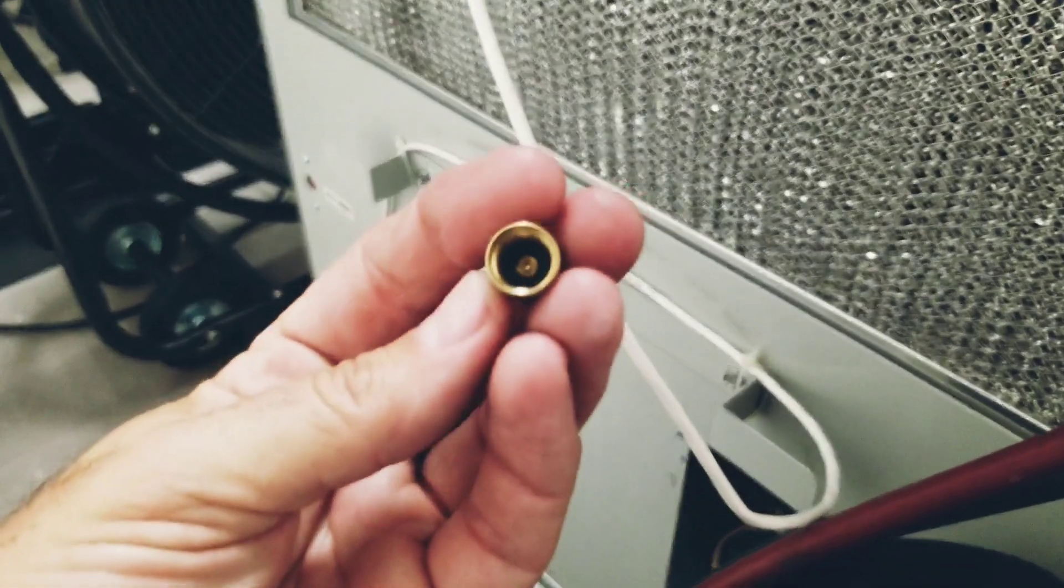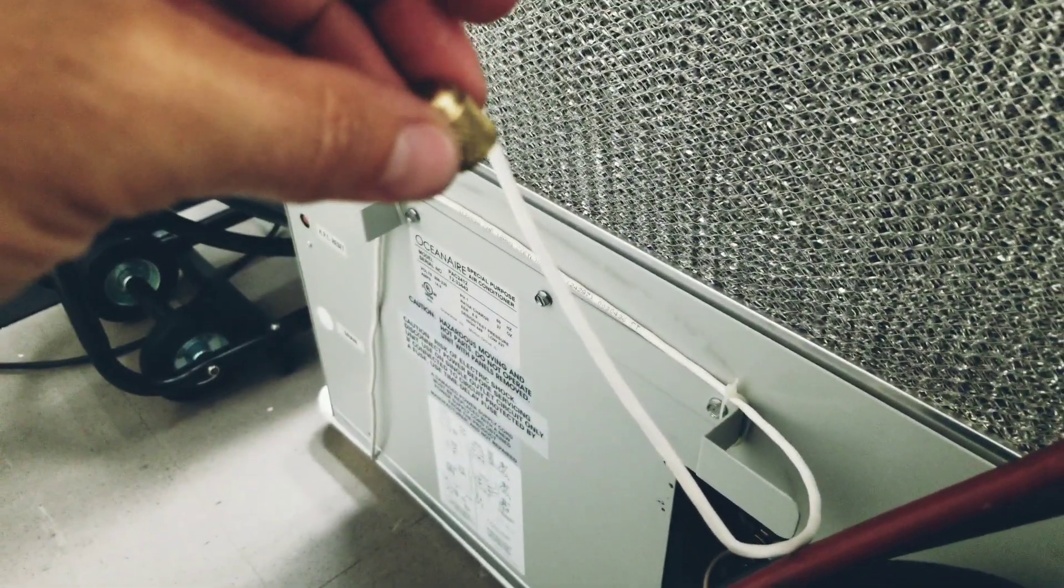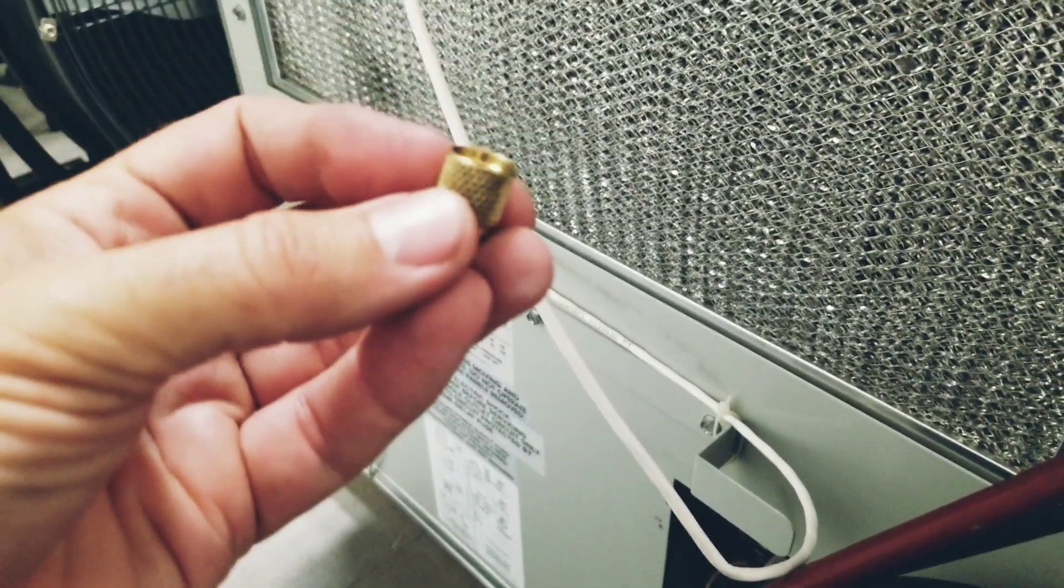It was actually leaking from this service port right here on the liquid line. What happened is the cap, even though it's got rubber, must have vibrated loose and the Schrader was leaking.